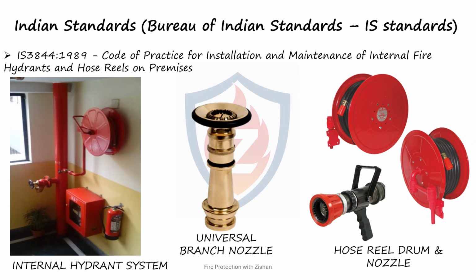The internal hydrant system serves as the first line of manual firefighting within a building. When properly installed and maintained in accordance with IS 3844, it provides rapid access to water, supports emergency response efforts, and significantly enhances the safety of occupants and property. In simple terms, the hydrant system supplies water, the hose reel delivers it to the fire location, and the branch nozzle helps direct the water effectively onto the fire. Together, these components form a reliable firefighting system that plays a crucial role in emergency fire protection.